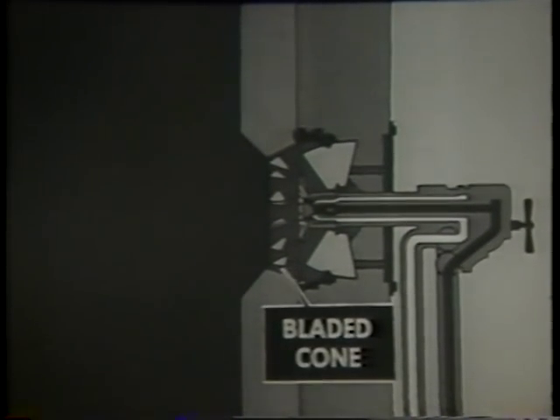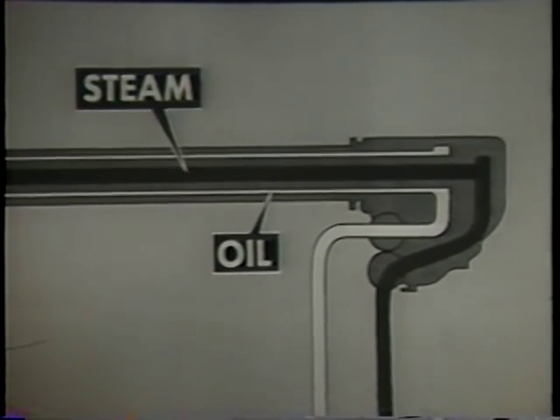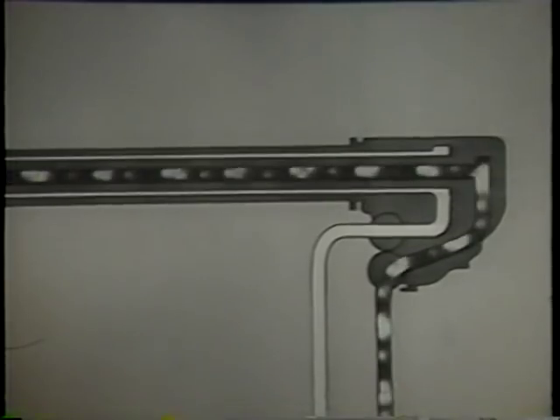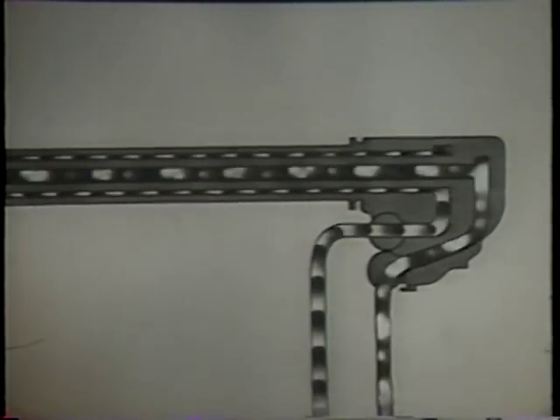The steam atomizing burner is similar in many respects to mechanical atomizing burners. It has an air register with diffuser, bladed cone, and air doors. However, the barrel of the burner has passages for both fuel oil and steam. High pressure steam passes through the central passage in the burner barrel, while oil, under low pressure, passes along outer passages. The steam heats the oil. The steam and oil mix in the sprayer plate, and the mixture passes through openings or jets in the plate and emerges as a fine mist. Meantime, the air from the forced draft blowers is entering the register and mixing with the oil spray.